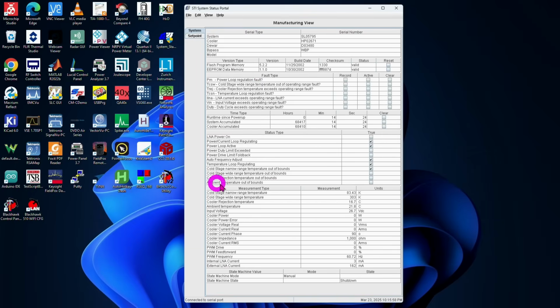There's also another temperature sensor, which is the narrow temperature sensor. It only kicks in around 83 Kelvin. It's going to do a different calculation, and that is, of course, maxed out right now. So we are reading the wrong thing here. Ambient around 21, and the cooler temperature about 16.7. It thinks it's a little bit cooler than it actually is. But other than that, it's pretty self-explanatory. I can put this thing into initialization and then it starts to cool down, and then we should be able to see this temperature go down.